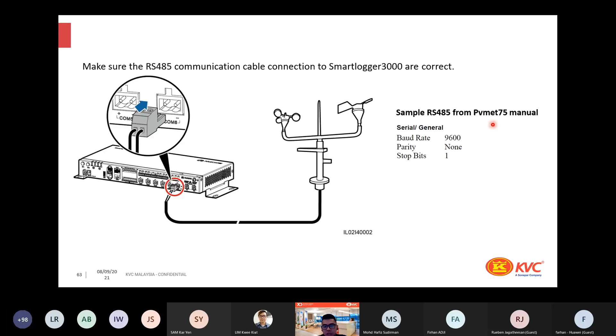Always ensure, for example with this PV referring to PVMet 75, that the polarity of your RS-485 cable is correct - positive to positive, negative to negative. If it's reversed, you won't be able to find your weather station. Always remember this.